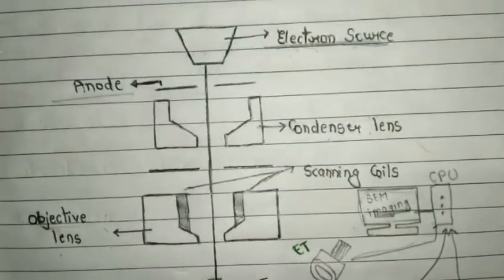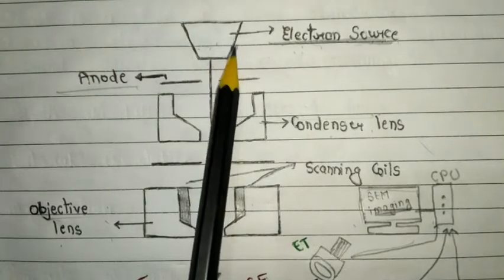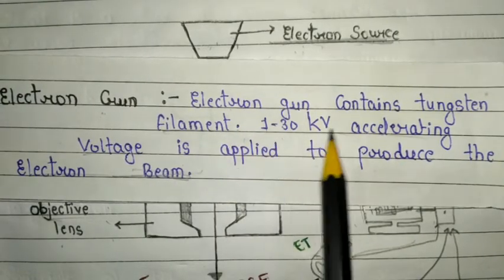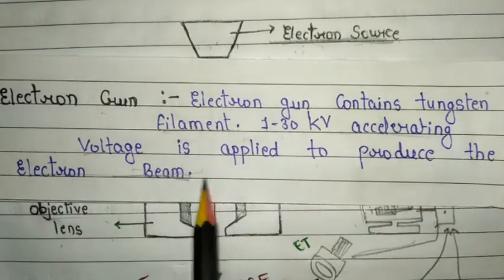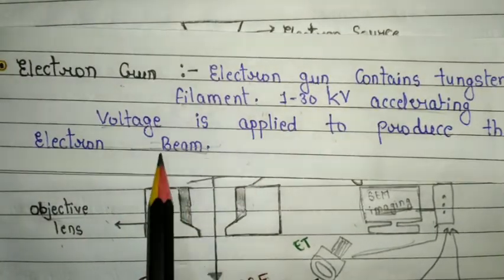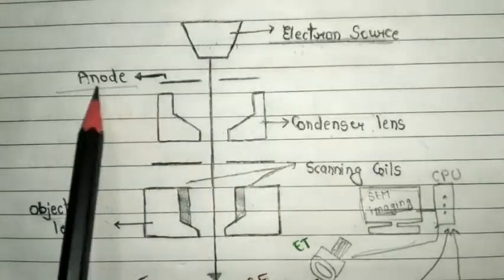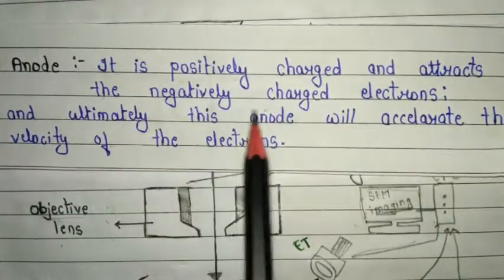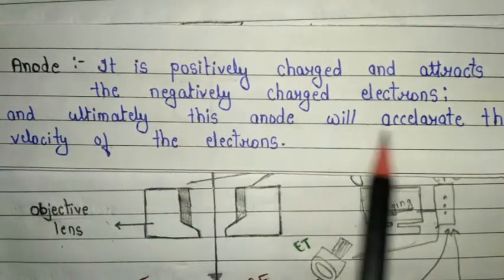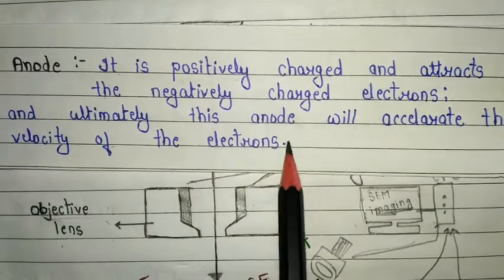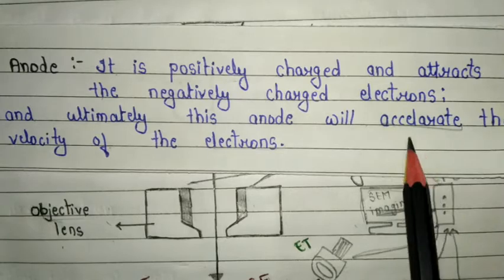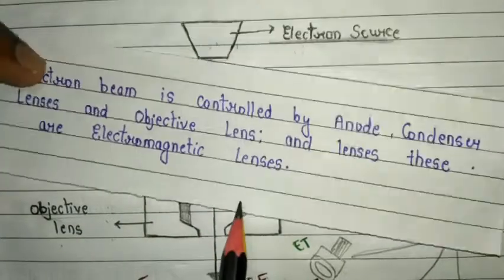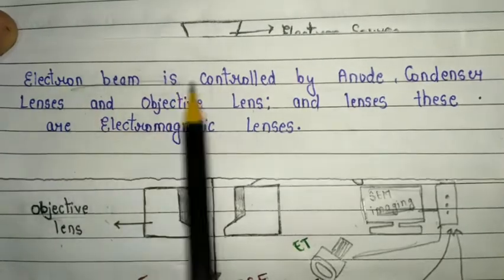For the electron source, we use an electron gun. The electron gun contains a tungsten filament, and an accelerating voltage of 1 to 30 kilovolts is applied to produce the electron beam. The electron gun is used to produce the electron beam. The anode is positively charged and attracts the negatively charged electrons, and ultimately accelerates the velocity of the electrons. The main work of the anode is to accelerate the electron beam. One very important point is that the electron beam is controlled by the anode.